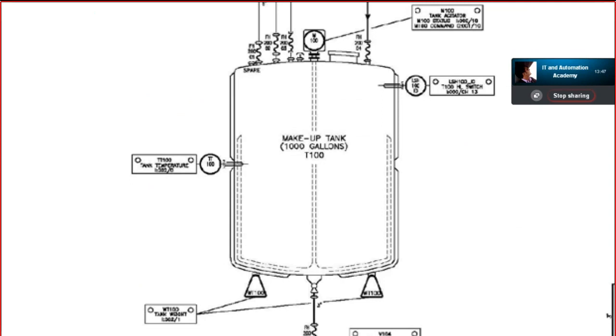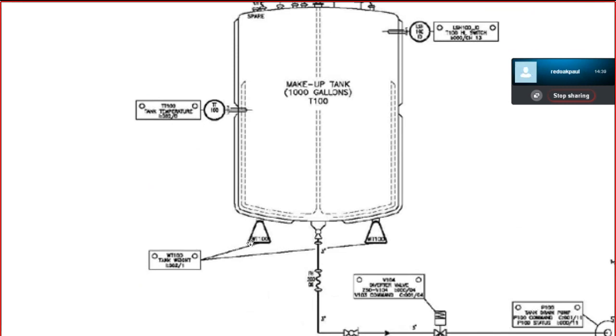On the left side you can see a temperature transmitter named TT100. On the top of the tank there is a level switch which lets you know that the level in the tank is full, so you have to stop the filling. On the bottom you can see a weighing scale — WT100 — with two strain gauges that will transfer the weight of the whole tank to the PLC system.